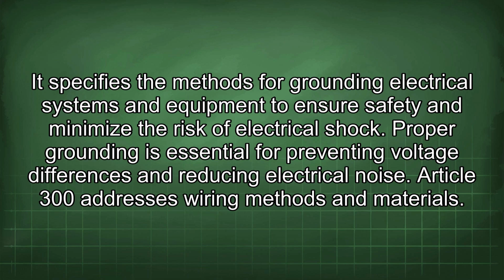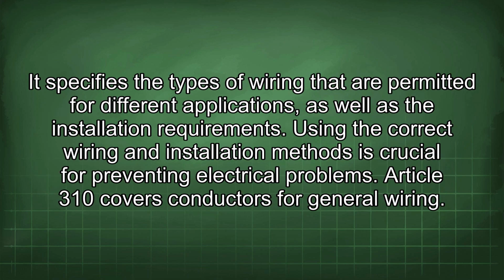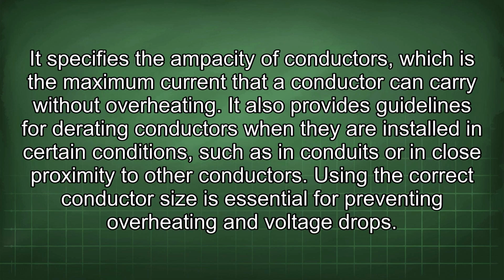Article 300 addresses wiring methods and materials. It specifies the types of wiring that are permitted for different applications, as well as the installation requirements. Using the correct wiring and installation methods is crucial for preventing electrical problems. Article 310 covers conductors for general wiring. It specifies the ampacity of conductors, which is the maximum current that a conductor can carry without overheating. It also provides guidelines for derating conductors when they are installed in certain conditions, such as in conduits or in close proximity to other conductors. Using the correct conductor size is essential for preventing overheating and voltage drops.